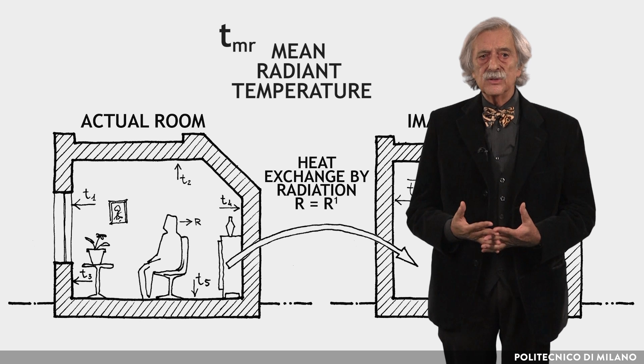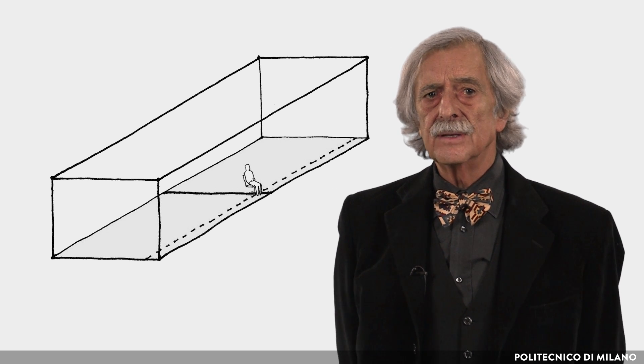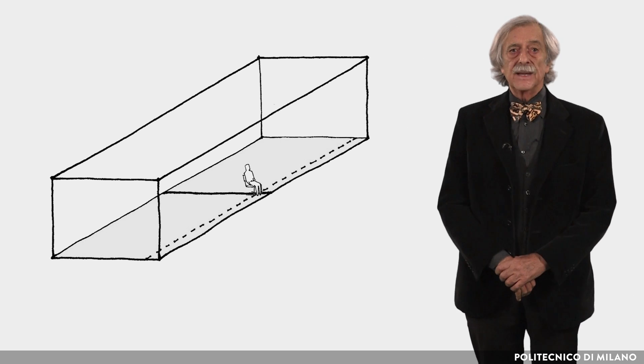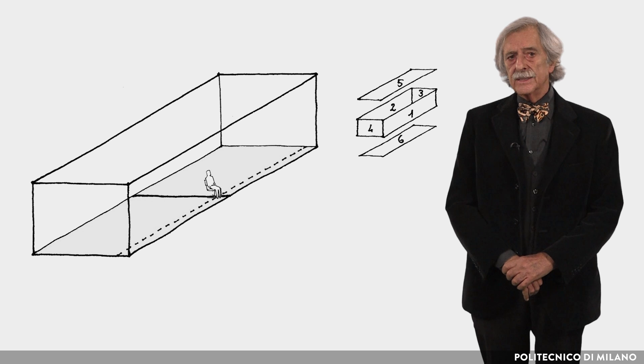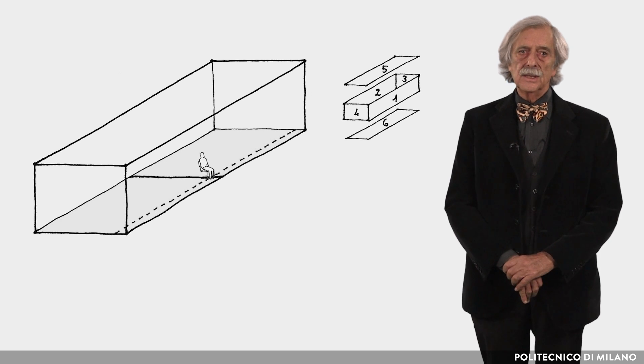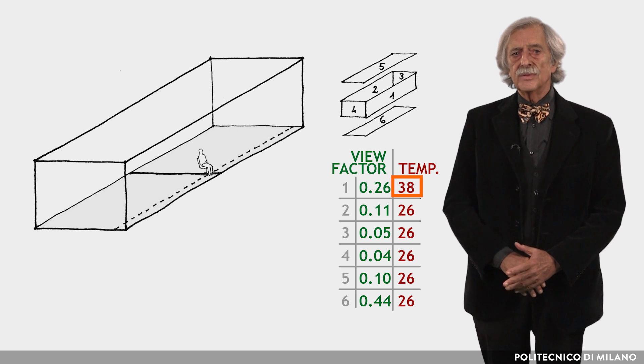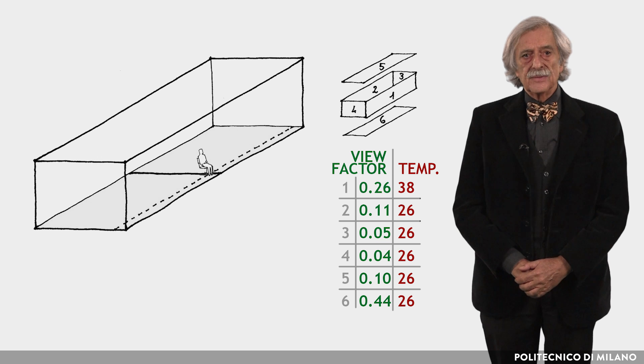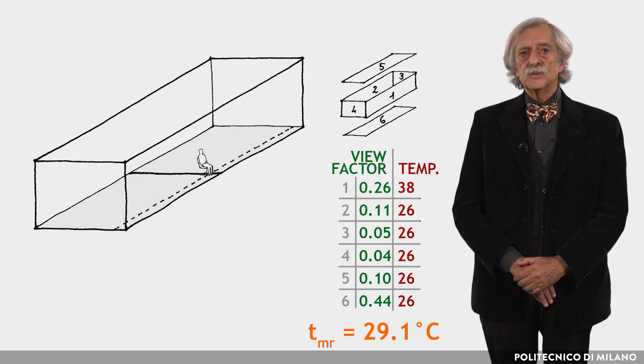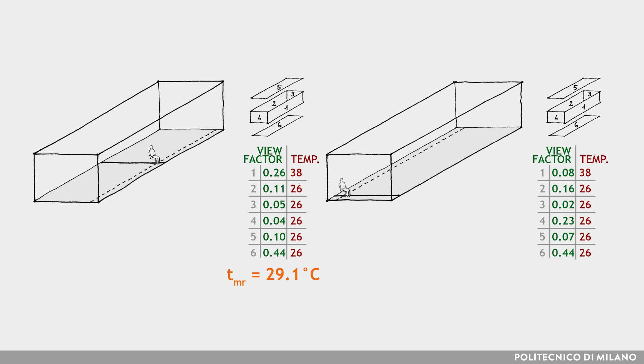It is important to note that the mean radiant temperature is a function of the position at which it is measured. This is a particularly critical aspect in rooms with large glazed surfaces. Consider a room, as shown in the figure, in which three walls are opaque and one is glazed (surface number one). Suppose the glazing temperature, due to outside temperature and solar radiation absorbed, is 38°C and all other surfaces are at 26°C. If the person is close to the glazed surface, the mean radiant temperature at that position is 29.1°C. If instead the person is in a corner far from the glazed surface, the mean radiant temperature is lower: 26.9°C.